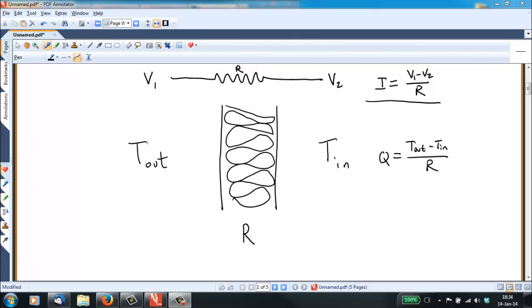Now this Q is for one small section of the wall. Q_BND, which is the Q, the heat flowing through the entire boundary, is going to be equal to the sum of all of the Qs of all of the sections of the house. So for example, there's a certain amount of heat that flows through the wall. There's a certain amount of heat that flows through the windows. They have much less resistance than your wall does. And we can sum these up in the same exact way that we sum up resistors in parallel for an electrical circuit. And we can come up with some resistance, which we'll call R star, which is a combination of all the resistances of all of the components of the envelope of the house, all of the components of the boundary of our control volume.